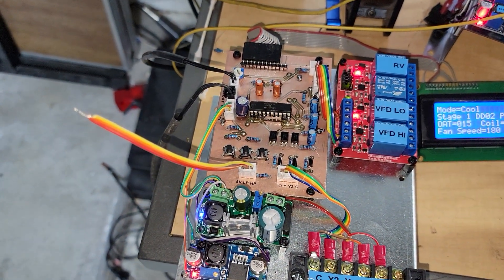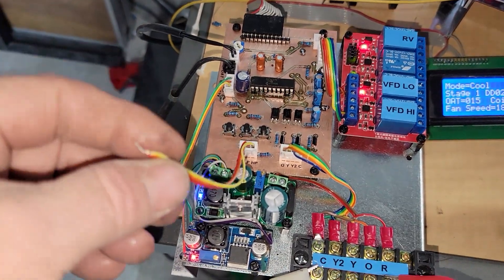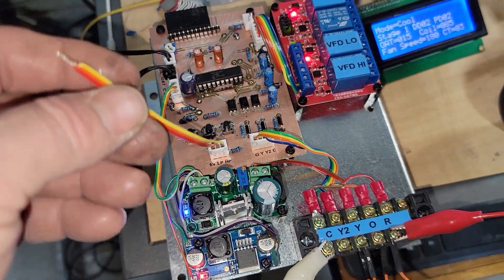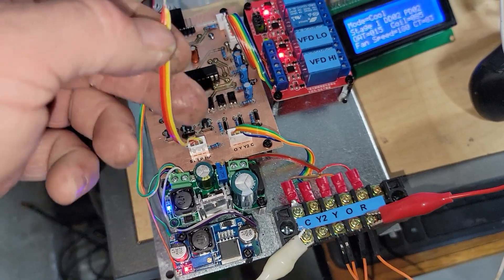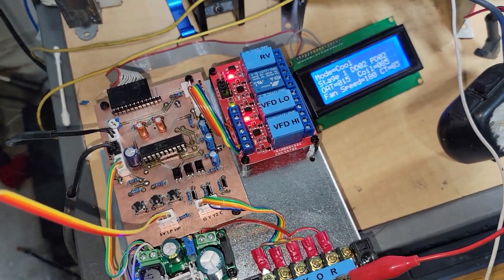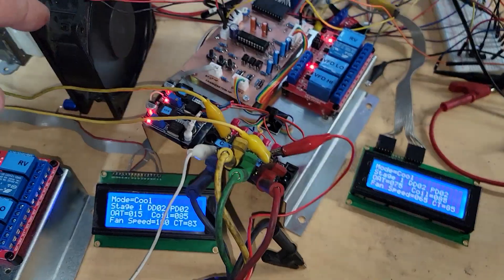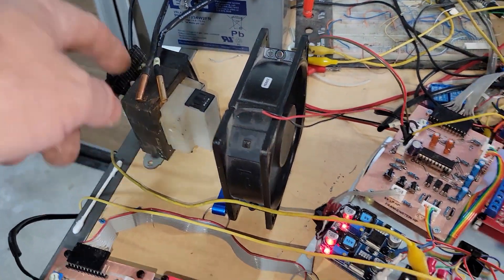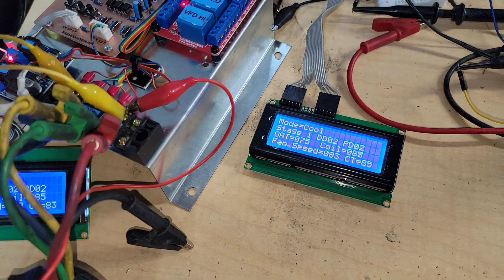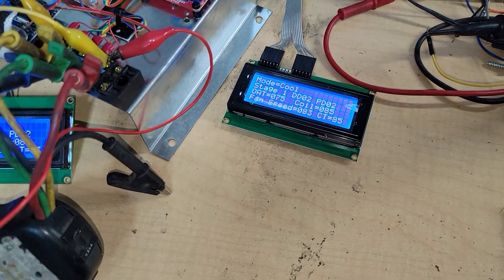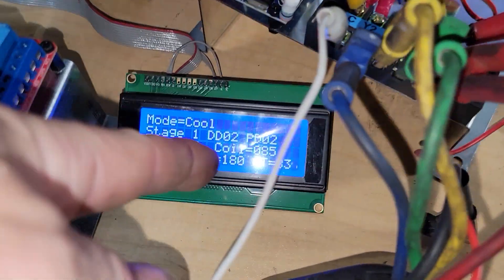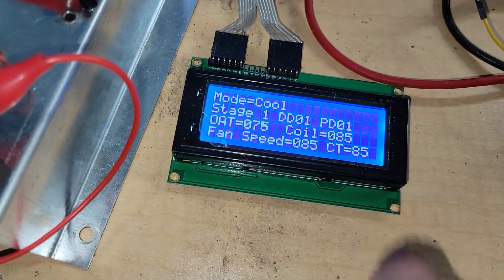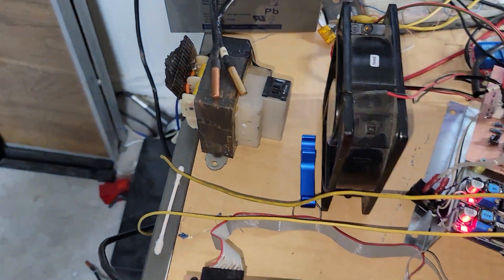Right now I just have them twisted together so it doesn't fault. This one's still running - I have the thermistors just laying on top of the 24 volt transformer. It's a very slow heat but I have it set just above the space temperature I'm standing in. These two sensors are both laying up there - 85 degrees coil, coil 85. They actually agree now that I've left them up there a little bit.